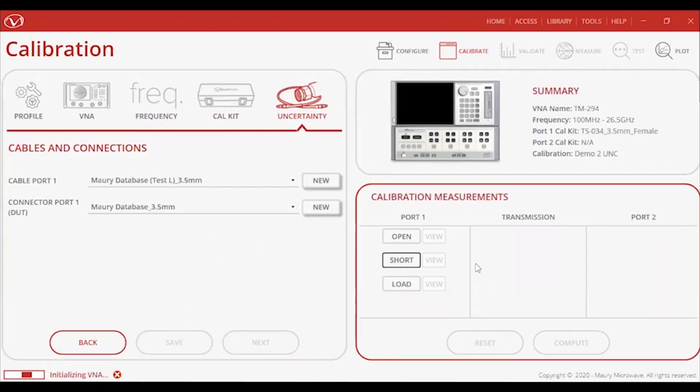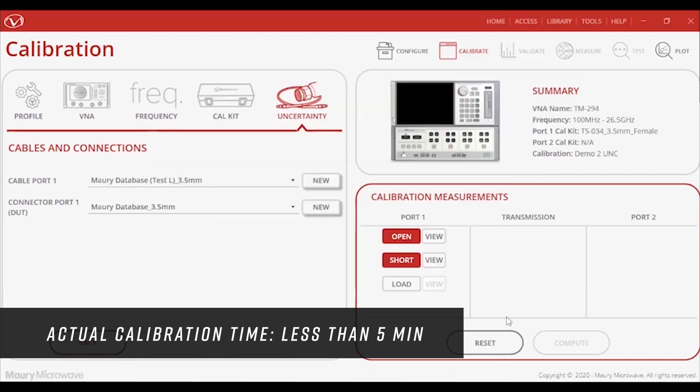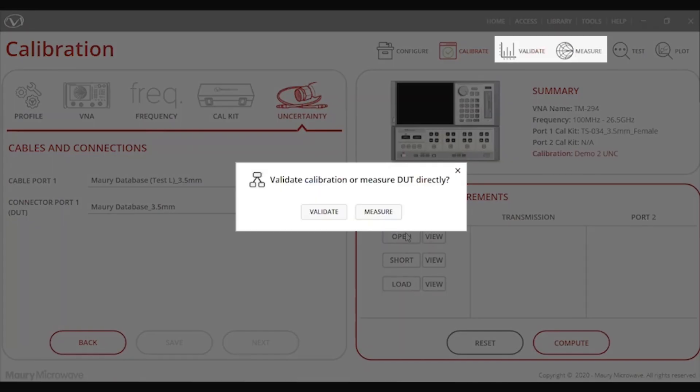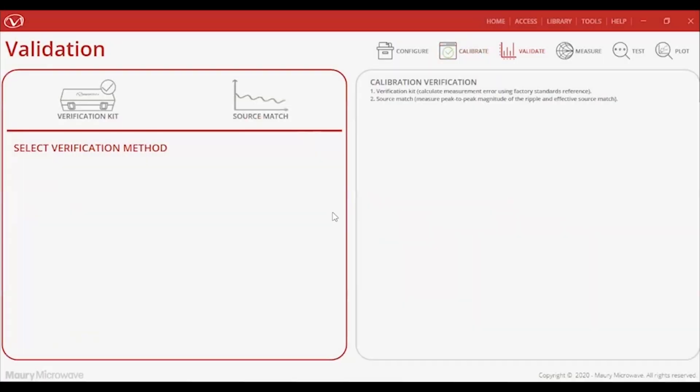Now, the software will prompt the user to go through the calibration measurement process of connecting the standards. For the sake of time, I'll fast-forward to the end of the calibration step. At this point, I now have the option to validate or start taking measurements, but of course, it is always recommended to validate your calibration and check if it meets the desired level of accuracy.